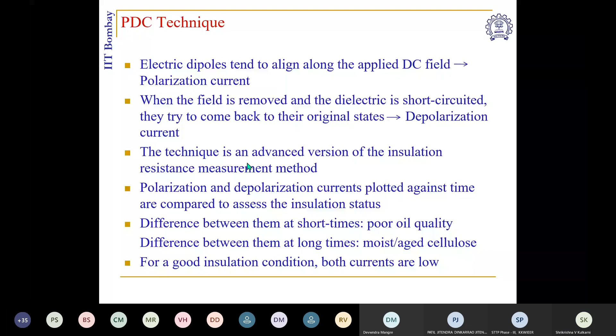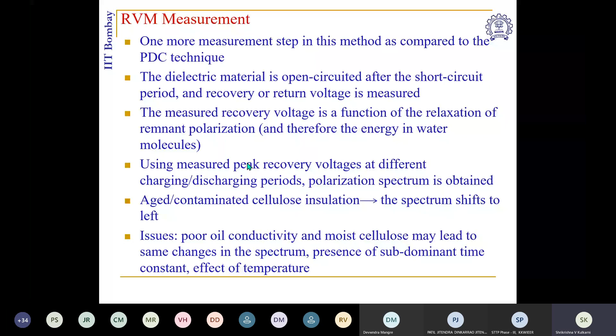Now the recovery voltage method involves one more step as compared to the PDC method, wherein the dielectric material is open circuited after the short circuit and the recovery or return voltage is measured. The measured peak of the recovery voltage at different charging and discharging periods can be used effectively to understand insulation condition. For example, if it is aged or contaminated insulation, the polarization spectrum obtained by plotting this measured peak recovery voltage at different charging and discharging periods shifts to the left if it is bad insulation. But there are some issues with respect to this RVM measurement, which are discussed in the literature. That's why researchers these days are not so excited by this RVM method. The PDC method in the time domain is more popular and established now as compared to RVM.